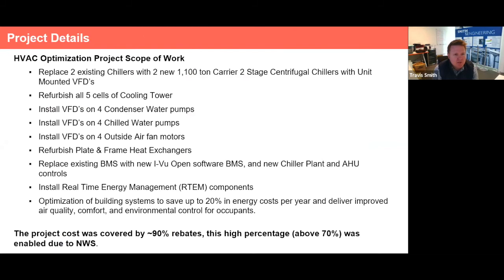Some project details: we replaced 2 of the existing 950-ton chillers with 2 new Carrier 19 XRV units, 1,100-ton VFD machines. We refurbished all 5 cooling tower cells, installed VFDs on condenser water pumps, chilled water pumps, and the outside air fan motors. Since this is rebate focused, the VFDs on the dedicated OA fans came later in the project as a change order to the application - that's a pretty smooth process to submit through Con Ed if you already have an approved application. It was just more scope we decided to add during the project.